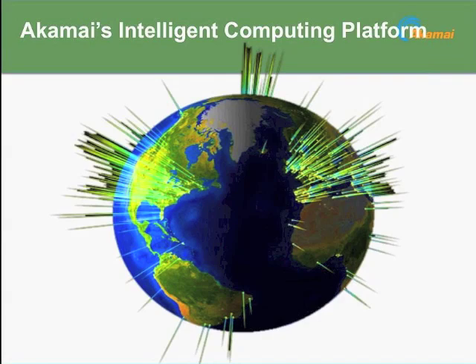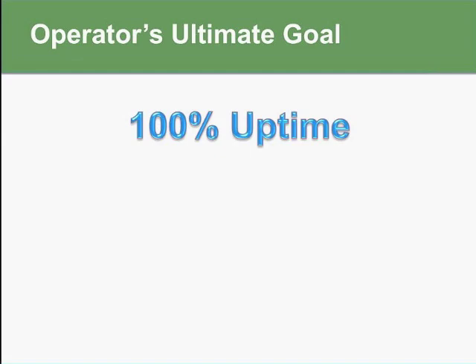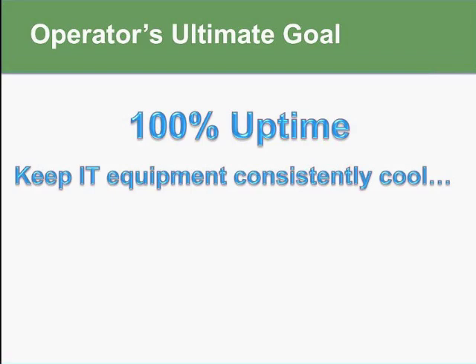And what's important to us, not only from an operational perspective, but obviously from a cost perspective, is that they not only provide 100% uptime, but also that they provide their services at low cost and high efficiency. I think everybody really understands that a data center operator's ultimate goal is 100% uptime of the IT equipment. So however you get there, so long as the IT equipment is up and running, everyone's happy. However, subsequent to that goal, that also means keeping the IT equipment consistently cool, because if you don't, you're going to have operational problems. But not only do you want to keep it consistently cool, you don't want to overcool because that's inefficient.